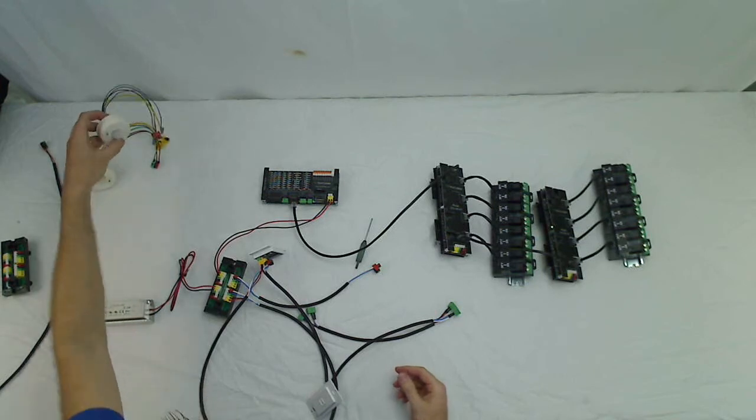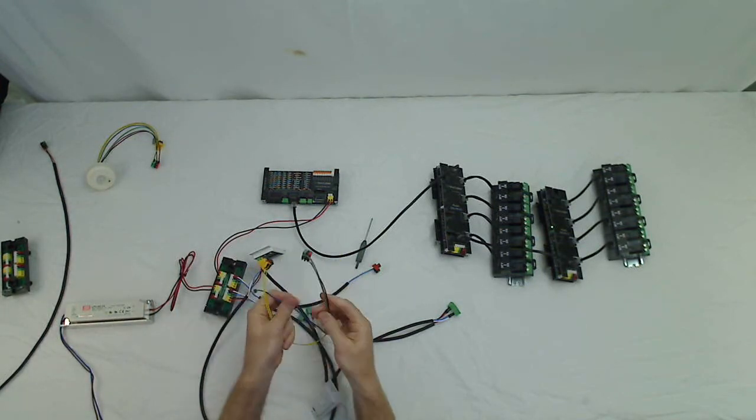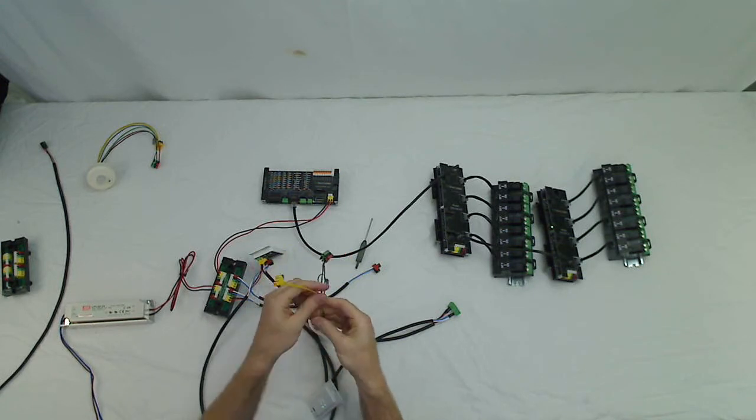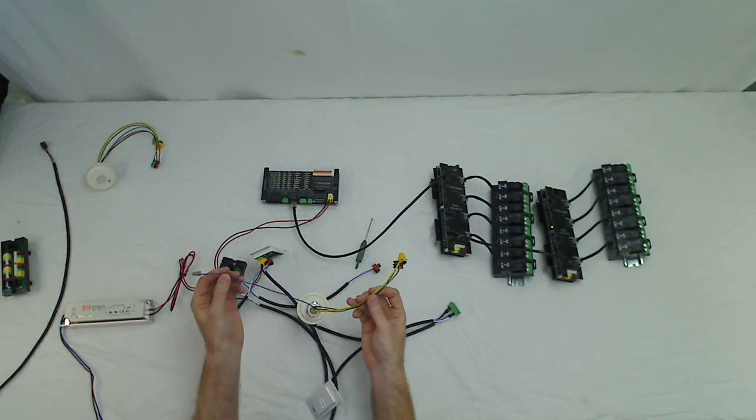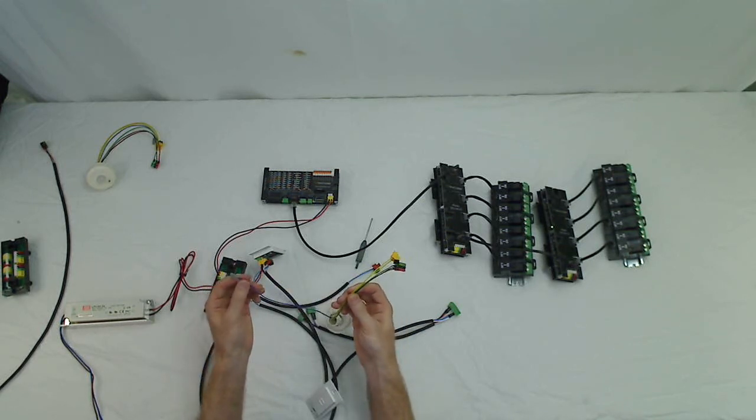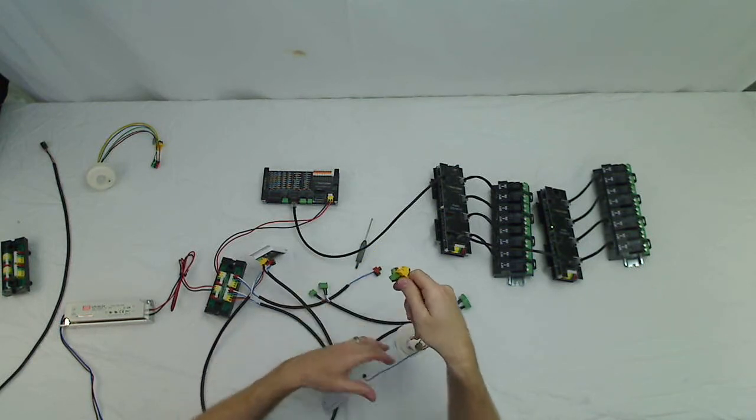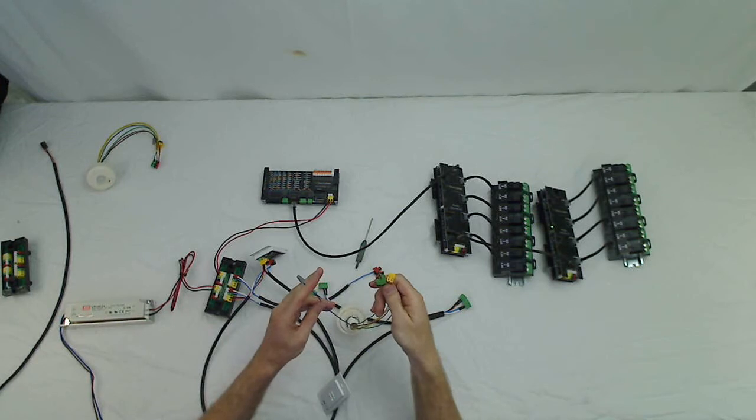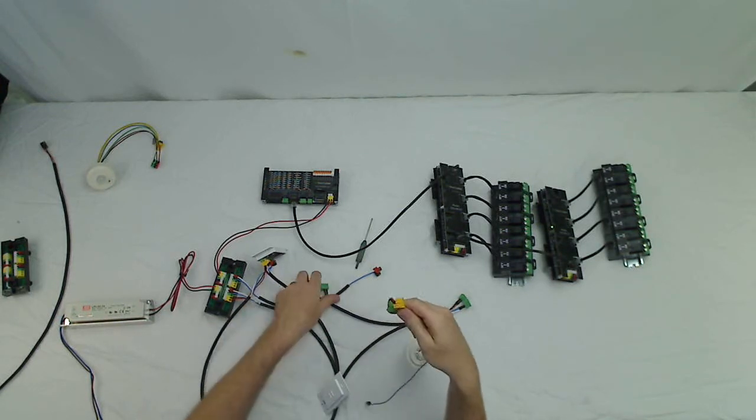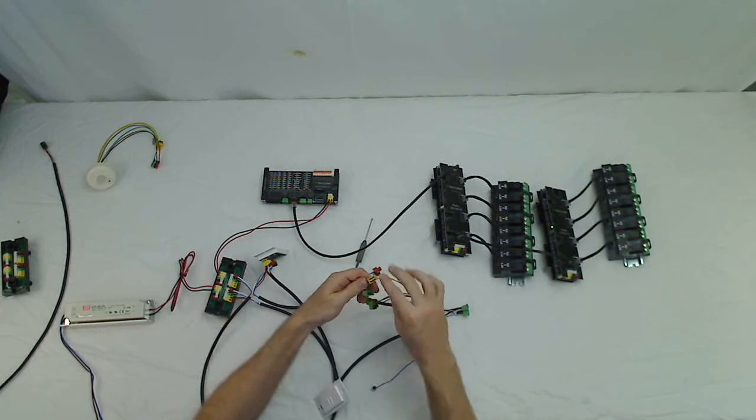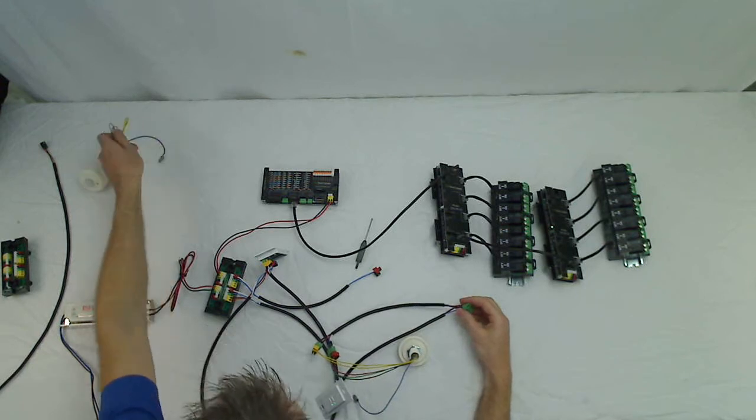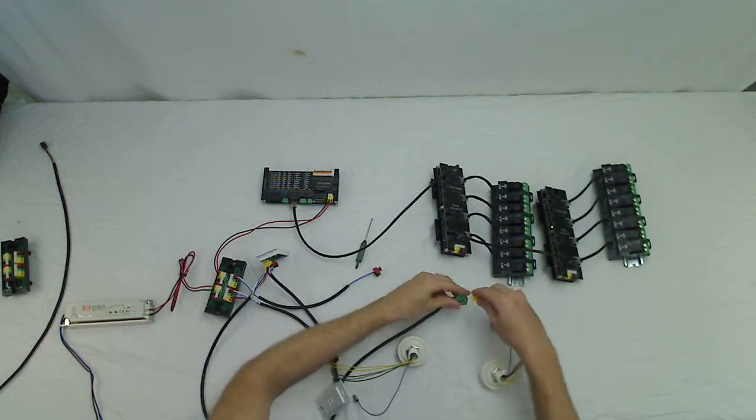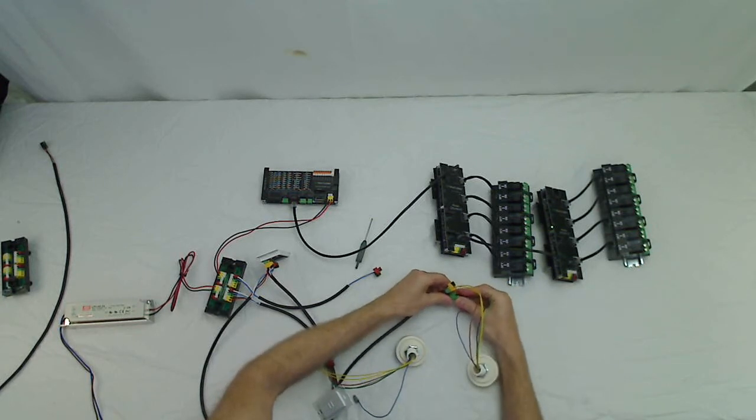And same for our sensors, same color code. The yellow-yellow is power. The green-black-red is for communications. And the blue wire is just a 24-volt dry contact. So if you want to use it for a third-party device, you could trigger a different device with that. And our last sensor.